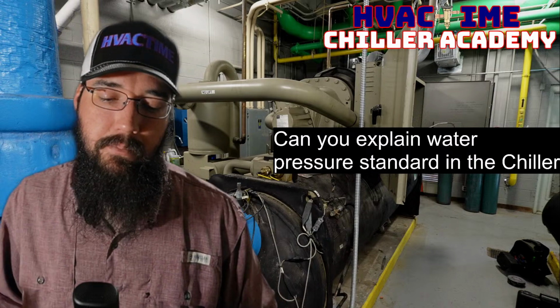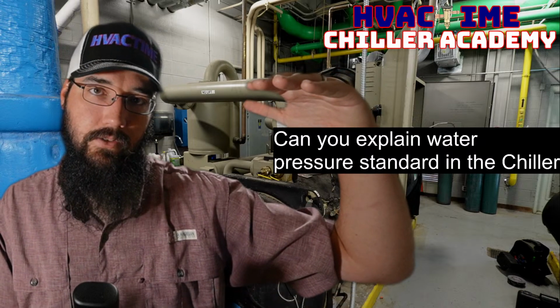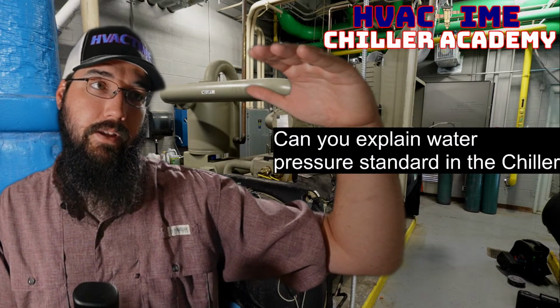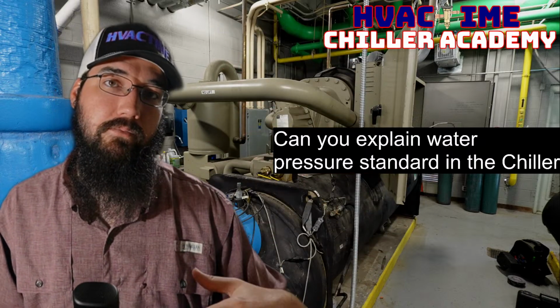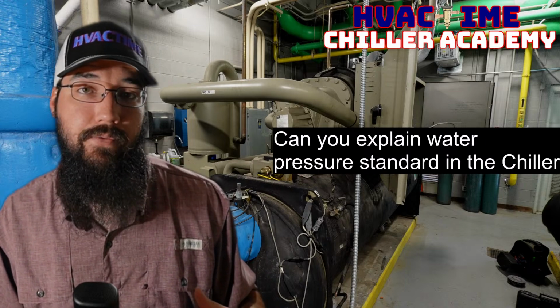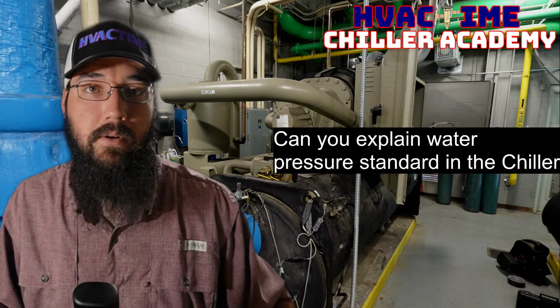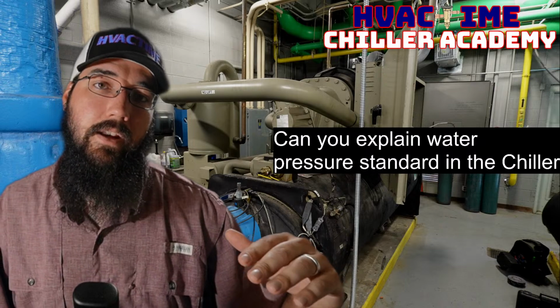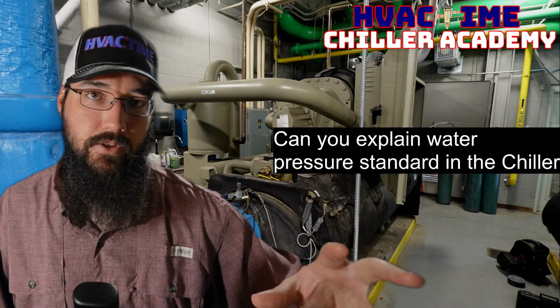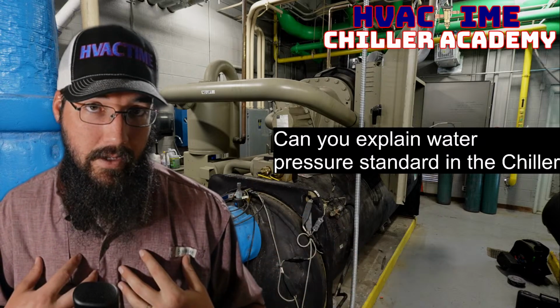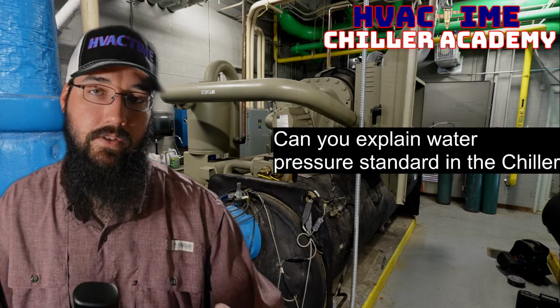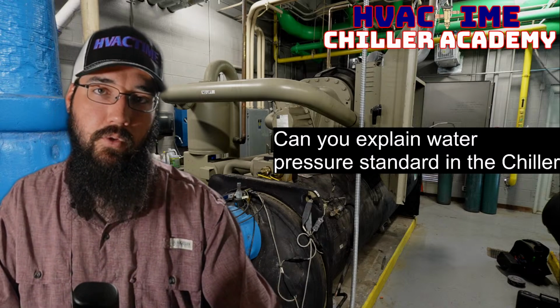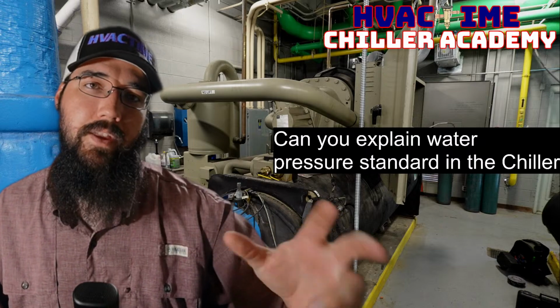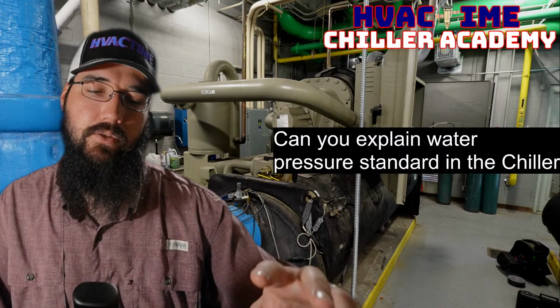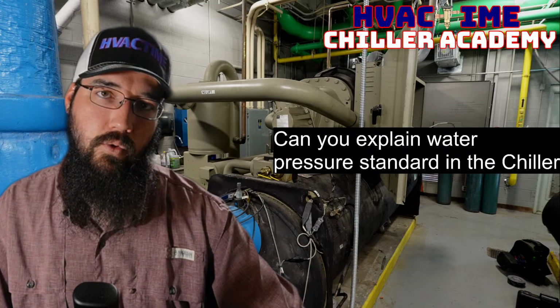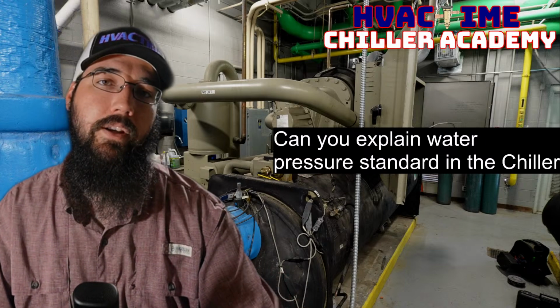So what you'll see is at the bottom of the loop, the pressure increases as the height increases. Even though at the top of the loop, we may still be at 0 PSI up here. As we increase height, we'll get to the point where down here we may be at 50, 60, 70 PSI at the base of the loop, the bottom, but still be at 0 PSI at the top. Now, if you are in a situation where your loop is running that low of a pressure at the top of the loop, you technically are pretty low on water by my standards. And I'm basing this off of the return side, the side coming back to the pump and the chiller, right? So I'm using that pipe as my standard with the pump online. So with that low of a pressure, you risk the cavitation, because once you start pulling the water down below 0 psi or close to 0 psi, that's when cavitation can start to happen.